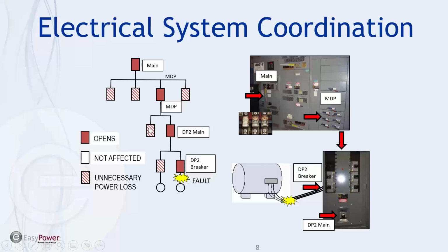So what if you go over to this panel and there's ventilation for a combustible dust area? Now you've just created an explosive atmosphere because your system is not coordinated and the wrong breaker tripped. So it's more sensitive than the other two. Either that has to be changed, but you have to make sure it's coordinated.